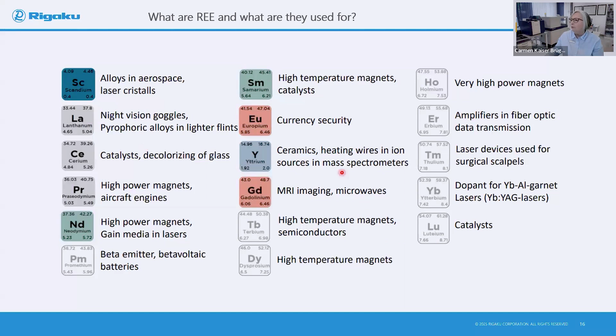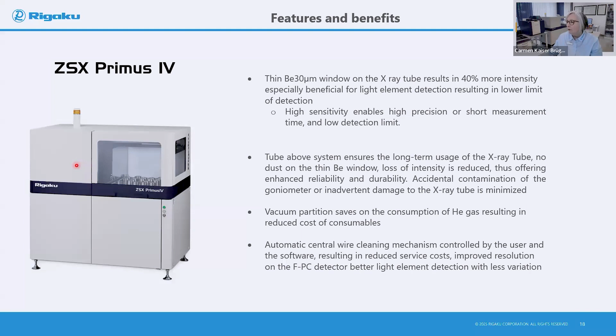So, of course, let's look at how we can take these minerals from the earth and try to estimate and accurately measure these rare earth elements using wavelength dispersive XRF. So if we take our Primus 4, the biggest advantage of this kind of instrument is that we have the geometry being above the sample. So this enables us to have a very high sensitivity and precision with the lowest limits of detection, which is what we would like to achieve. We also have a very nice system in that we can use automatic pressure control, which helps us to analyze these mineralogical elements that we would like to measure.